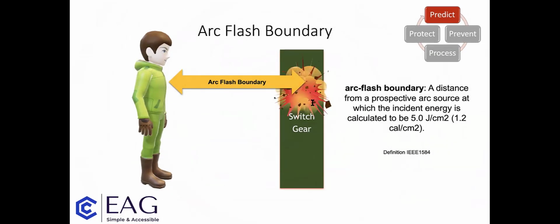The other thing is the arc flash boundary, that promise I'd come back to. The arc flash boundary is a distance from the prospective arc source at which the incident energy level is calculated to be 5 joules per square centimetre, or 1.2 calories per square centimetre. It's the onset of a second degree burn, which is used to determine that.